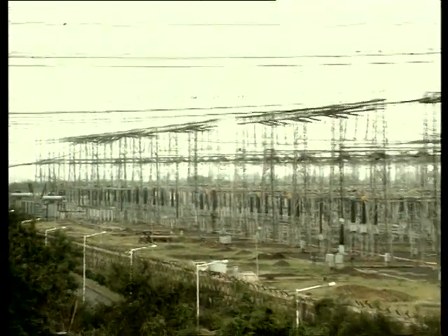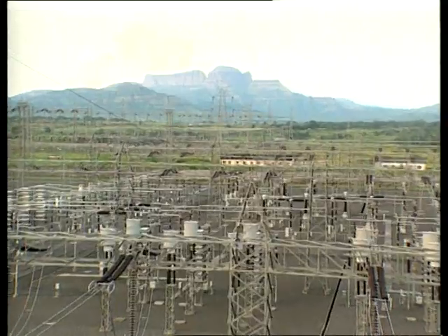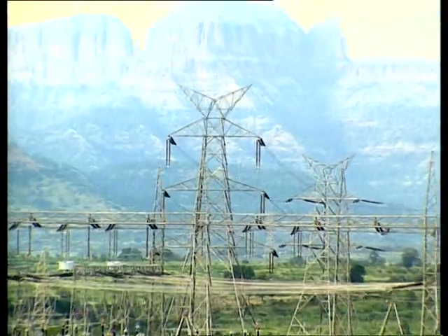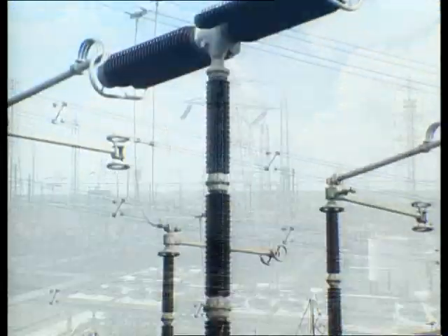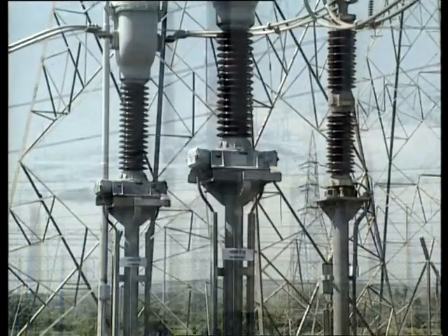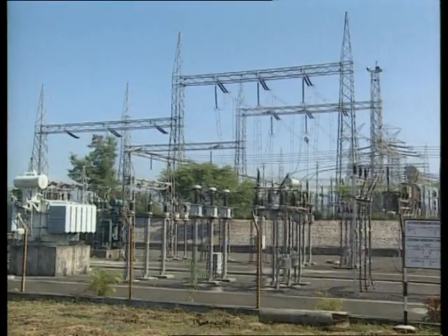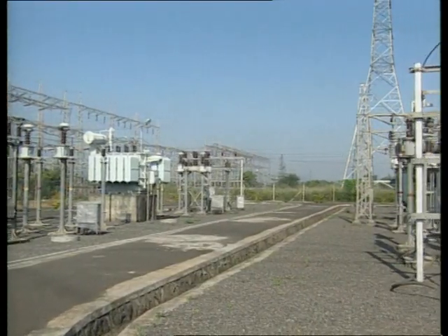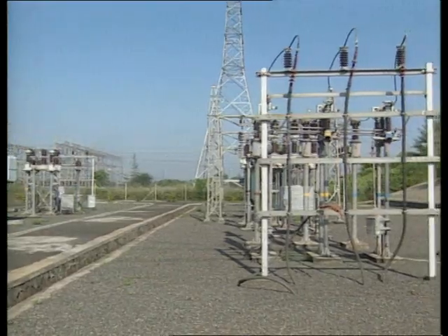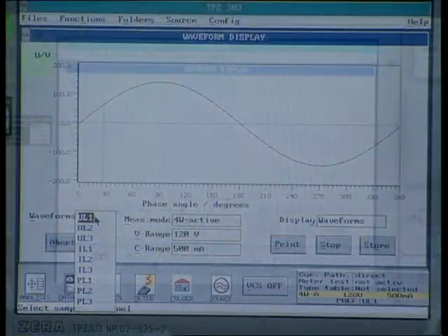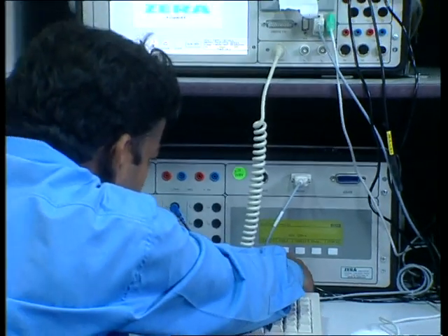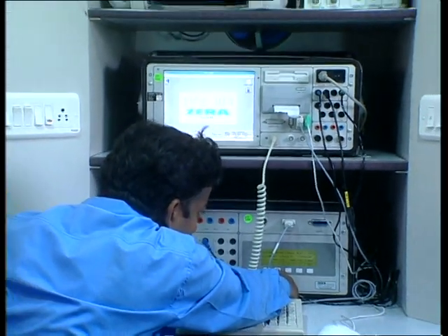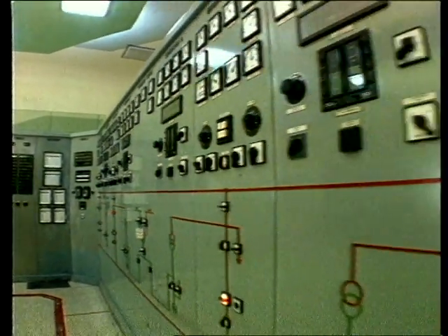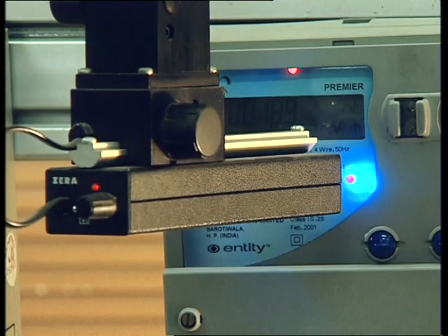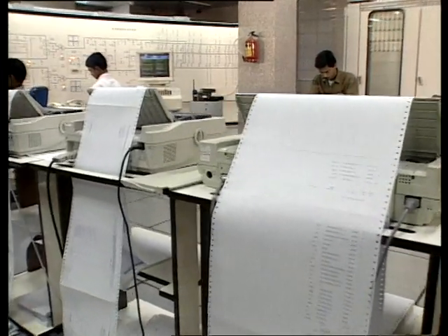The main challenge for the Indian power sector is the reduction in its abnormally high transmission and distribution losses. The extra high voltage and high voltage substations are the main hubs of power exchange, where electricity worth millions of rupees is transferred every day. Accurate measurement of these power transfers is the key to better energy accounting. Substation instruments are calibrated periodically to ensure that the revenue registers are under check.